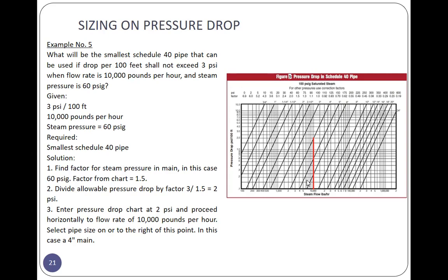So, ng pressure drop. Pressure drop yan ha. For other pressure use, pressure drop kasi table. What will be the smallest schedule 40 pipe that can be used if drop per 100 feet shall not exceed 3 psi when flow rate is 10,000 pounds per hour and steam pressure is 60 psi gauge. So given: 3 psi per 100 feet, 10,000 pounds per hour, steam pressure 60 psi gauge. Required: the smallest schedule 40 pipe. Solution, step 1, find the factor for steam pressure in main. In this case, this is 60 psi gauge, ang factor mo is 1.5.